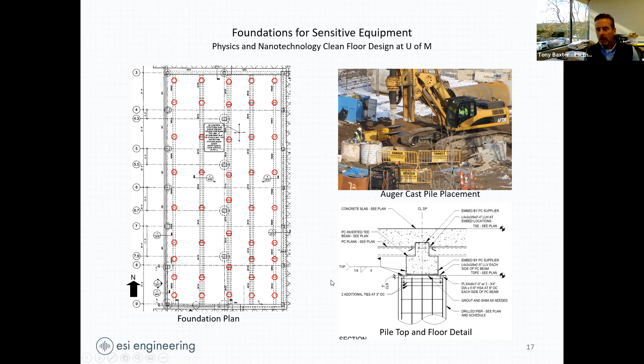The edge of the building to the center of this on-ramp was maybe 80 to 90 feet, fairly close, with a lot of truck traffic coming down the ramp picking up speed. You might get a semi going 50 miles an hour, less than 100 feet from where the MRI is. We recognized this right away when they called us to check whether this was a good site for the MRI. They'd already leased the space and started building it out when we got the call.